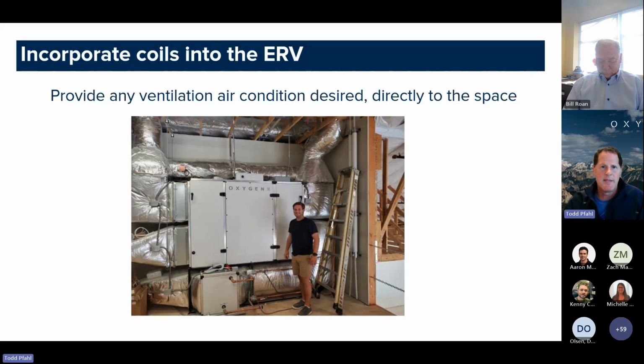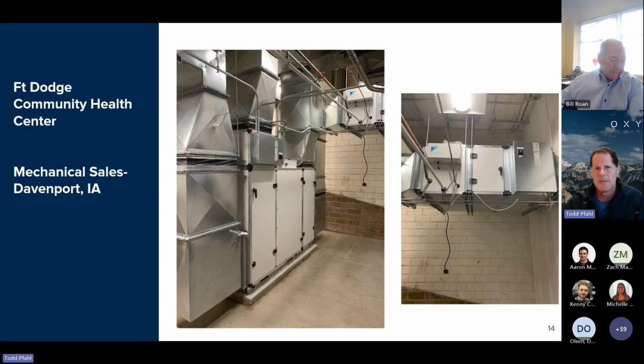This is an example of taking advantage of some of the flexibility that you can have with decentralized ventilation. Here we had a mechanical room that didn't have a lot of floor space, but did have a high ceiling height. So we were able to put an ERV up against the wall. You see there, the air comes out and does a 90-degree turn, and we actually put the heating element, in this case a hot water coil, below the unit. So again, just taking advantage of the space constraints to give the designers a lot more flexibility in how they're designing buildings.